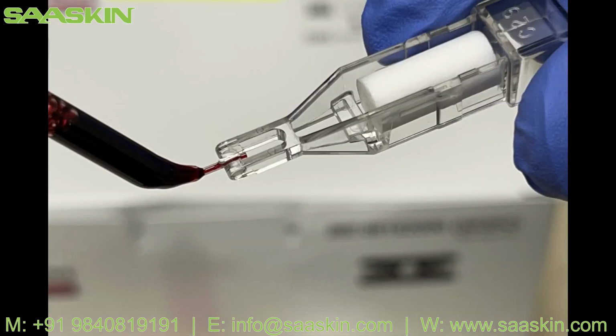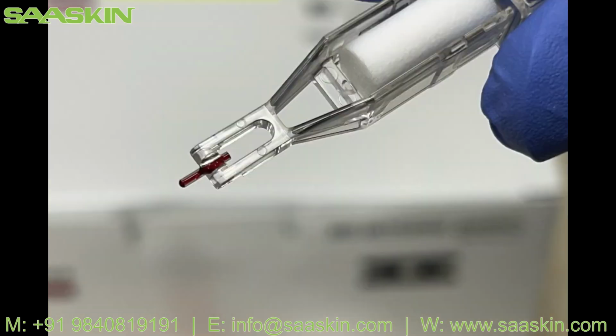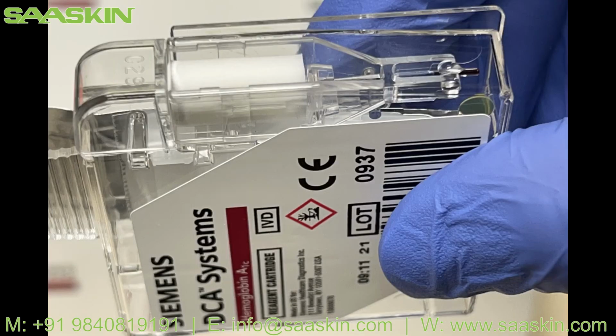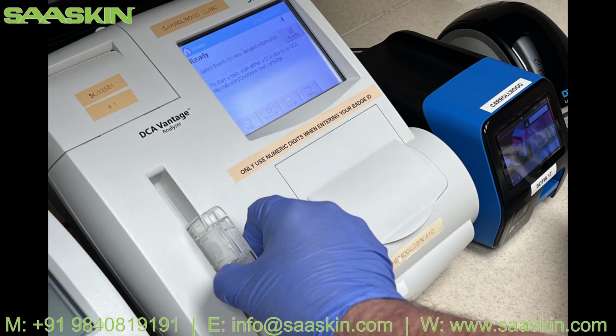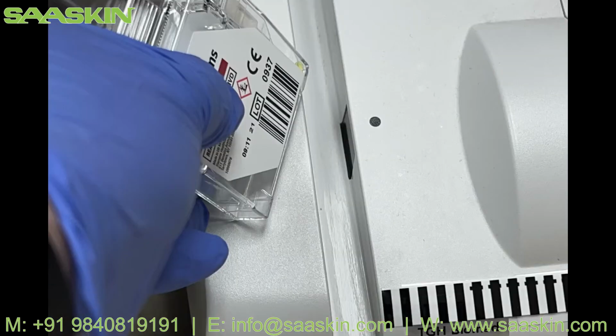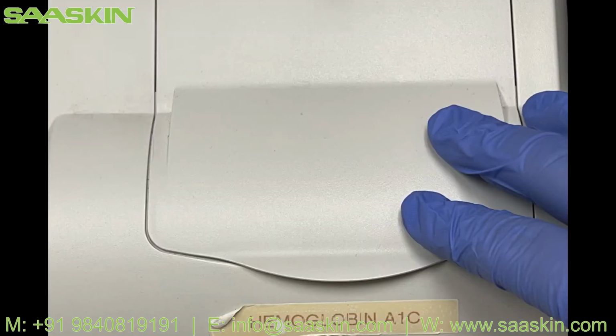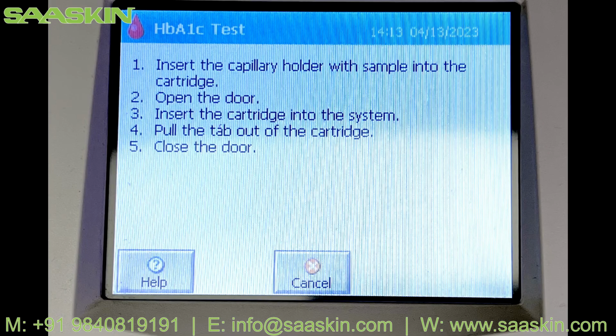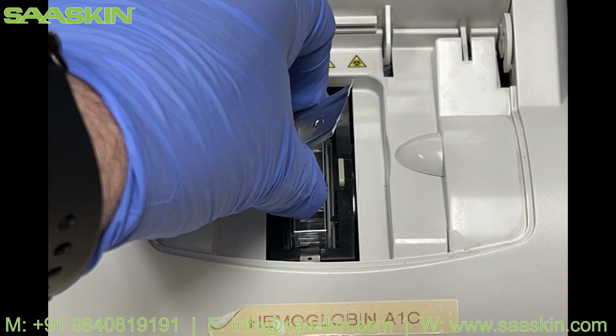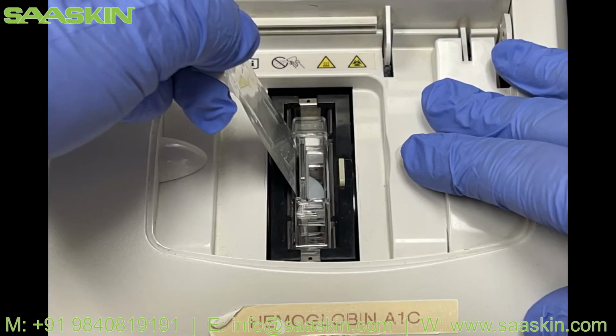Apply normal control sample to capillary collection device. Make sure there is no gap or overflow in the capillary device. Insert capillary collection device into the cartridge. Slide the cartridge in the bay for scanning. With the barcode facing the reader, open the meter door. The meter will instruct to insert the cartridge in the system until click. Then pull the foil tab out.